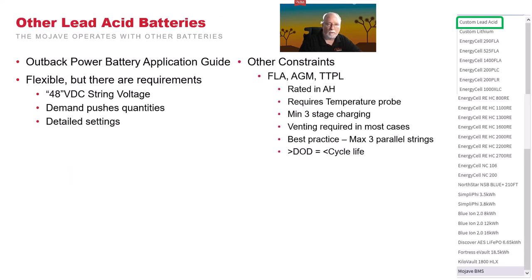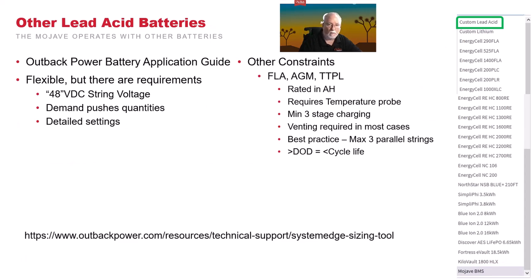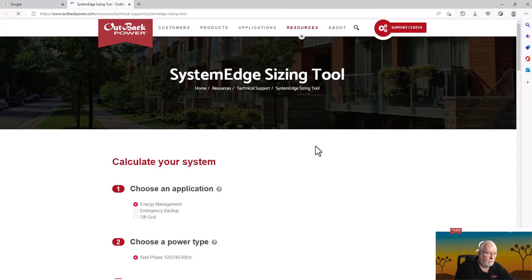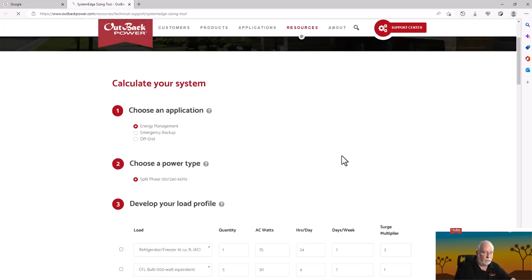Other lead acid batteries, so if you have a different kind of lead acid battery that is not listed on it, you can just put in the ampere hours. There's a setting that you go into in the unit to do that. It will require a temperature probe and follow best practices. If it's not defined outside of this, maximum 3 batteries per string. One of the nice things we have is the Outback SystemEdge sizing tool. You can get it off of our webpage. I just clicked on the link here. Really easy. If you're looking to set up something, you go in, you choose the application. Is it energy management? Is it emergency backup or off-grid?